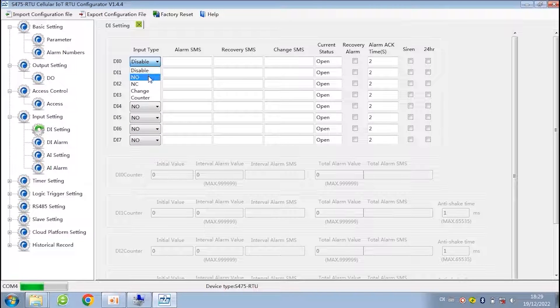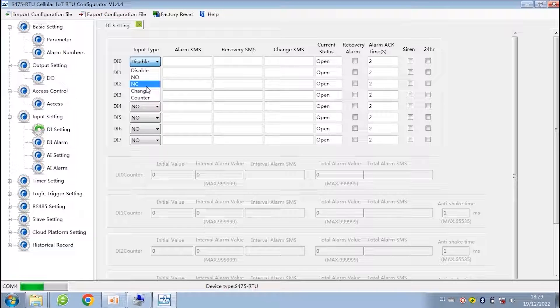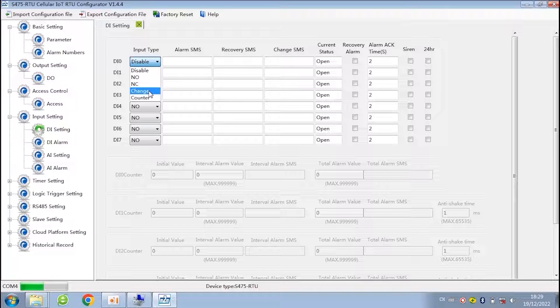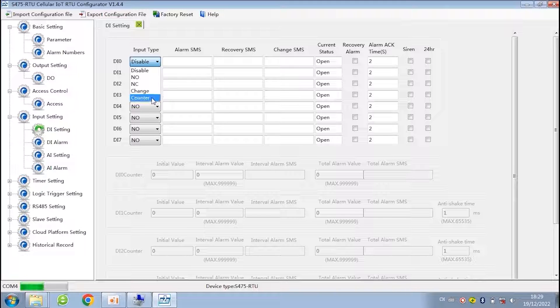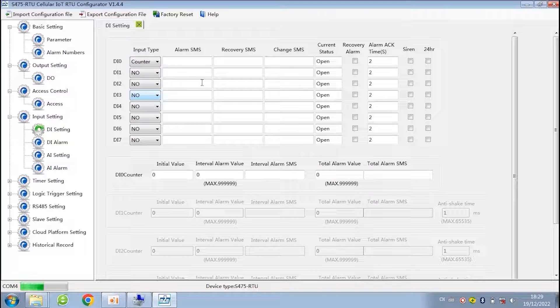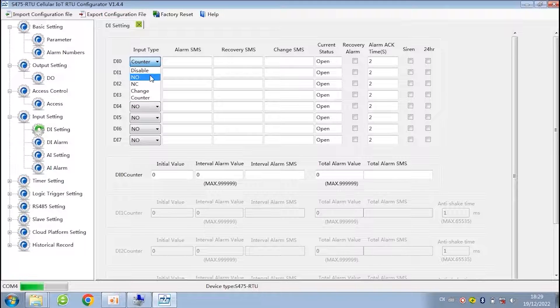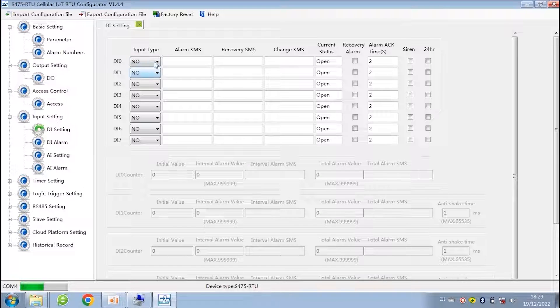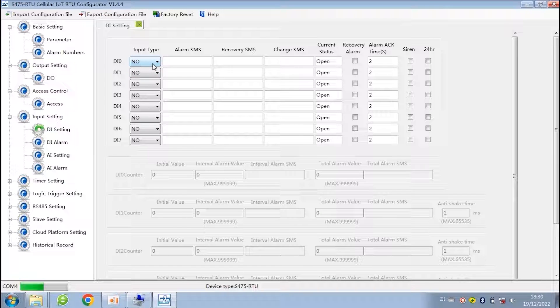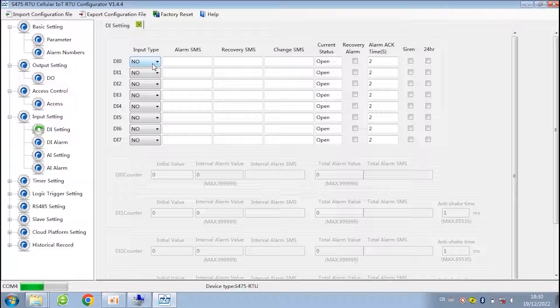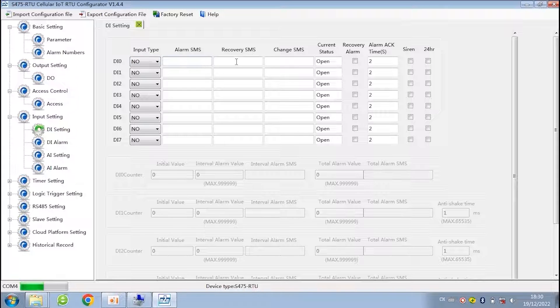Let's check the digital input setting. There are some options. First is disable, and normal open, normal close, change, and counter. If you choose normal open when it close, you will receive alarm. On the contrary, if you choose normal close when it open, the alarm will be triggered. And you can set the content of alarm SMS and recovery SMS.